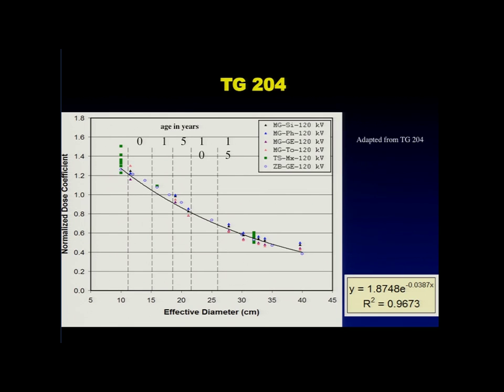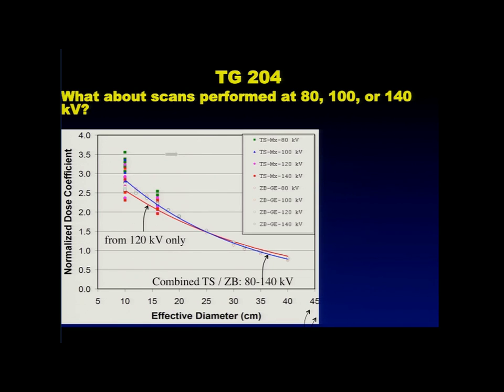So the 16 centimeter phantom's not a horrible representation of dose to a small child, but none of the manufacturers anymore are going to present CTDI vols for pediatric abdomens based upon the 16 centimeter phantom, because the IEC recently changed the rules so that they have to always use the 32 centimeter phantom for bodies.